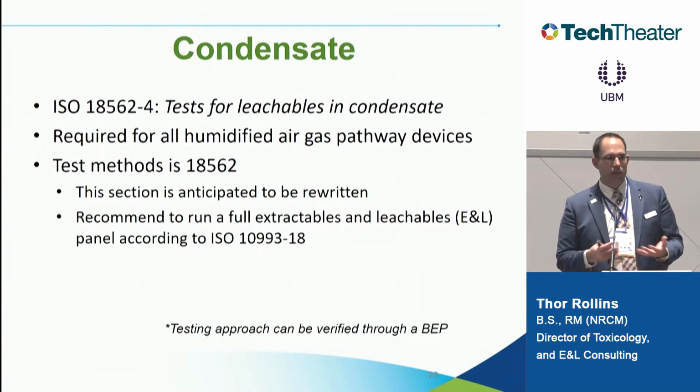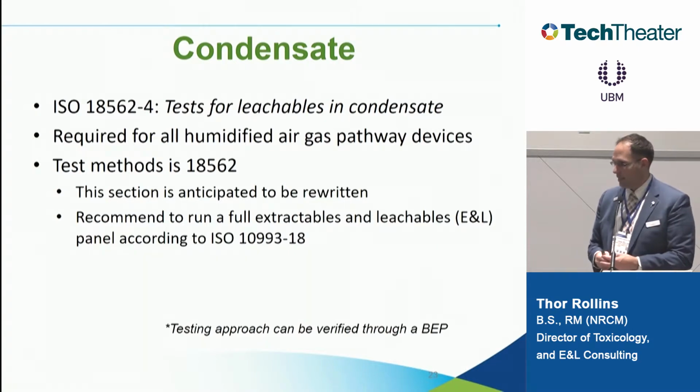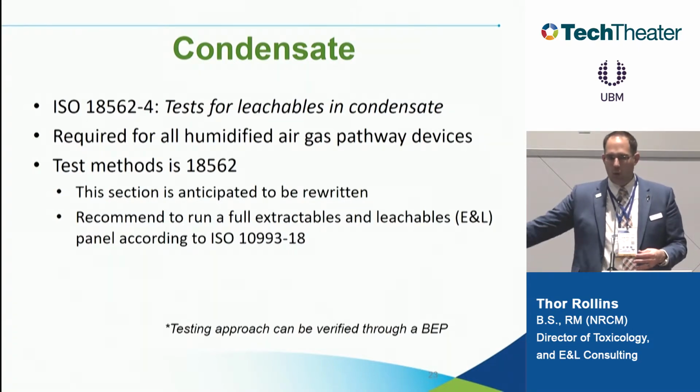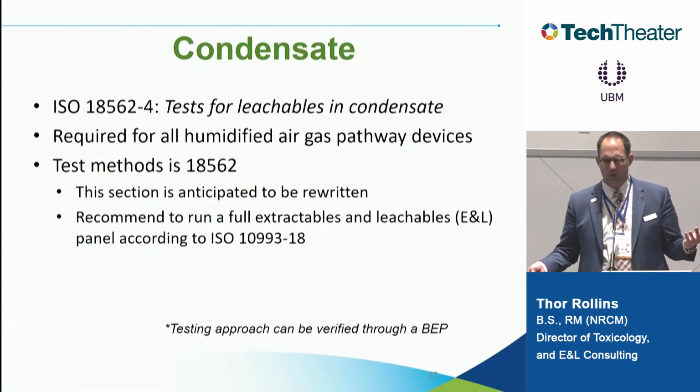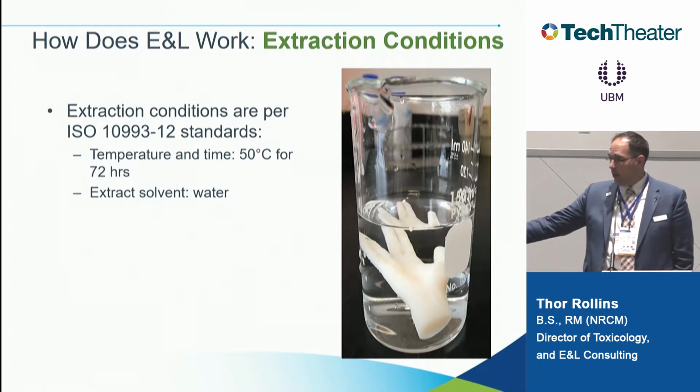Now, that's still worst case because you're using water instead of humidified gas. But most of the time we end up having appropriate safety margins and we're able to justify it as worst case. Still would not, though, chop up the whole device and put it into a container and extract it, unless that's how your device is used, which I wouldn't think so. So this is how we would recommend it.